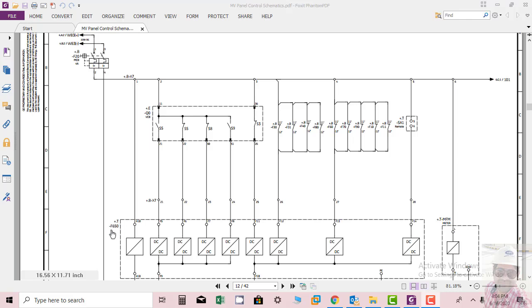This relay has two functions. Function 1 is to make the protection, and function 2 is also doing controlling, and it can be connected to substation automation systems for monitoring at local and remote stations.